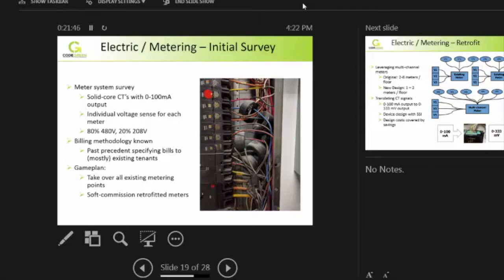In the case of solid core CTs, our experience is that unless you have a CT pretty close to an electric fault with a lot of heat generation near it, it's going to stay relatively consistent in terms of calibration — it's a solid state piece of electronics at the end of the day. We knew the output from this system was something our planned meters did not accept, 0 to 100 milliamp output, so we wanted to find a new solution that could either leverage the existing CTs or switch them out more cost effectively.